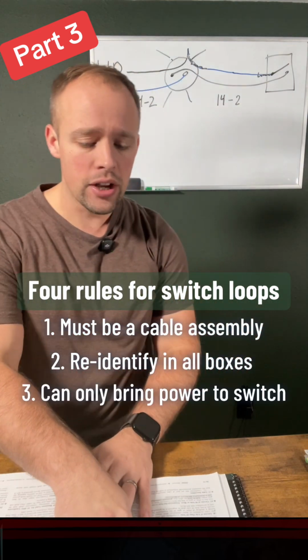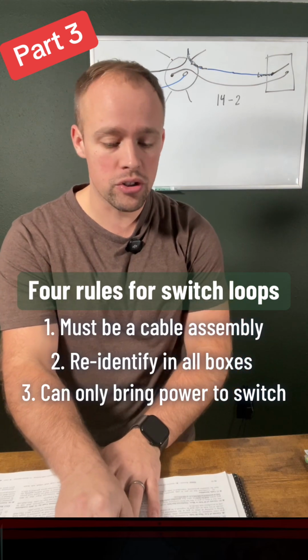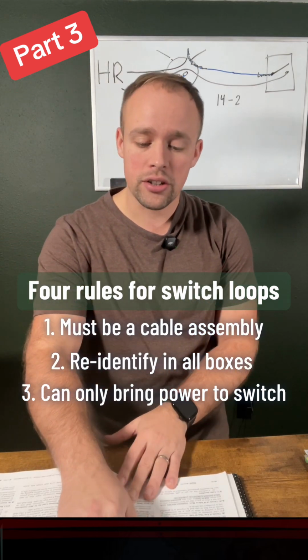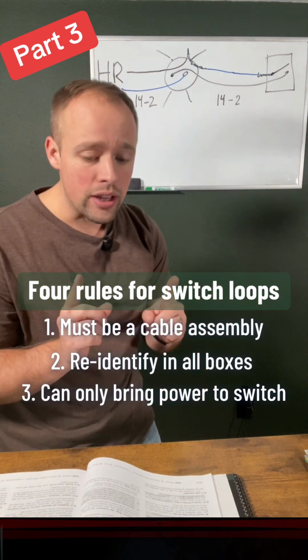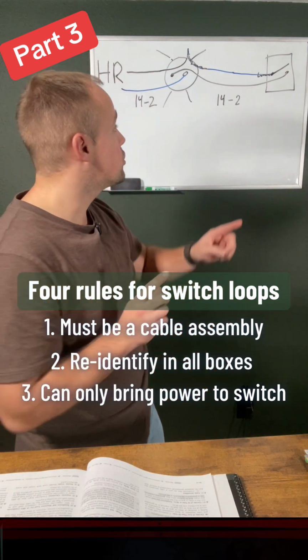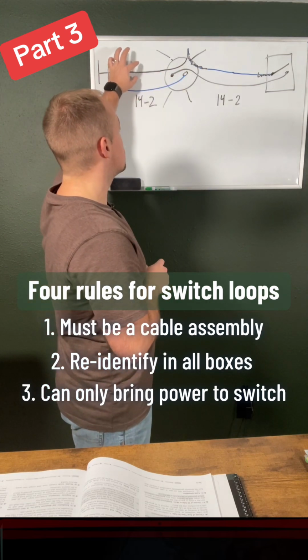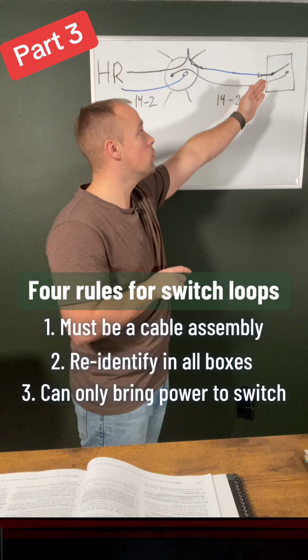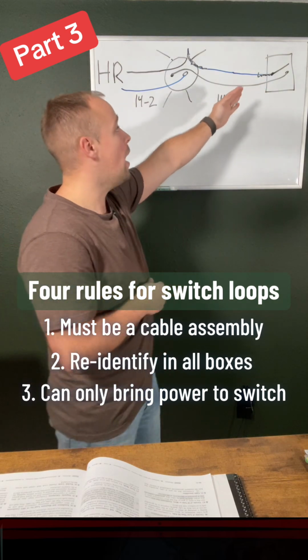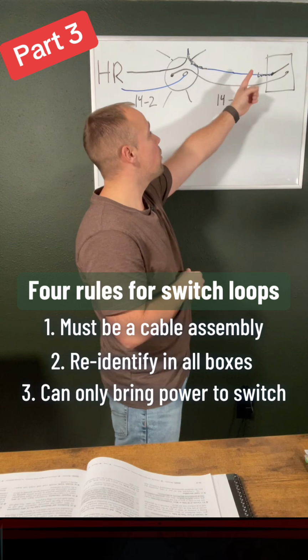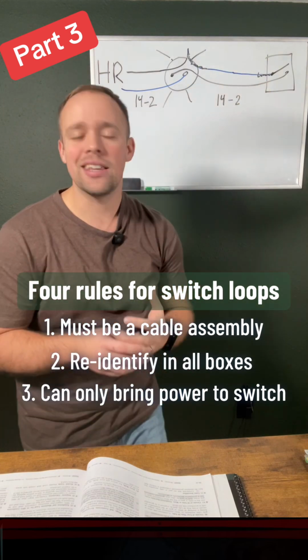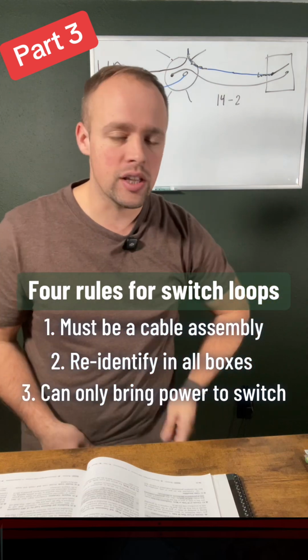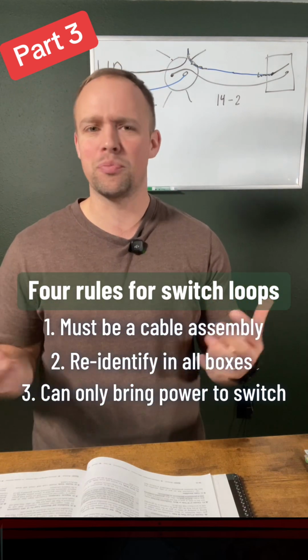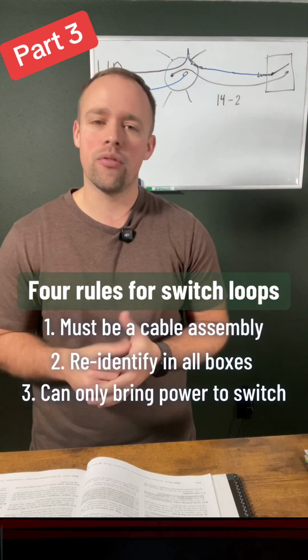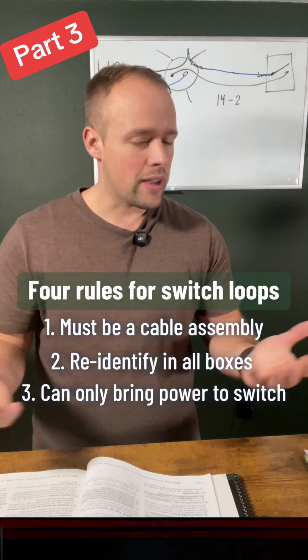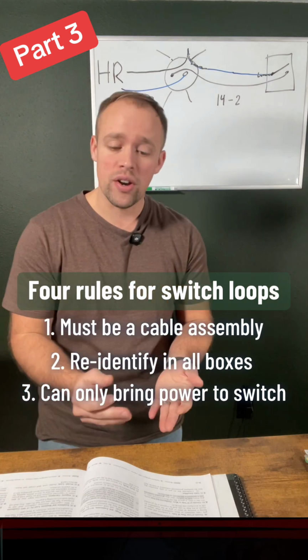Okay, here it says if used for single pole, 3-way, or 4-way switch loops, that re-identified conductor shall be permitted to be used only for the supply to the switch. Okay, as you can see, it is supplying power directly to the switch. We are not allowed to bring the power from that white wire to the light. Now, is it dangerous to do it that way? No. The inspector is not going to say, hey, you almost burnt the place down. He's just going to say, it's a silly code violation, just switch it, okay, just to make it code compliant. Okay, so those are 3 rules written down here.